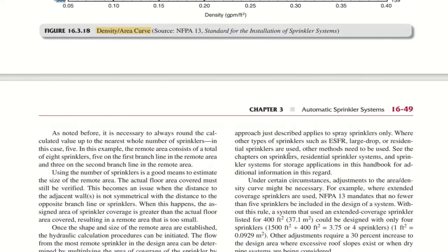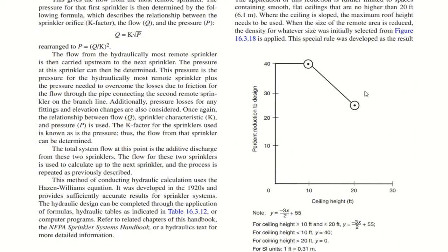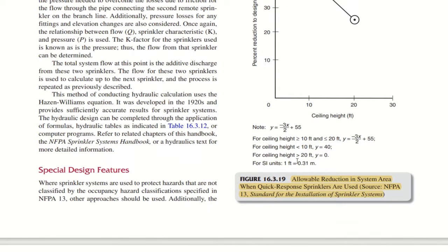If we consider quick response sprinklers in light hazard, then the density will be 0.1 gpm per square feet. However, the area of sprinkler operation can be reduced. So the hydraulically designed area can be reduced. That can be found from this graph. So this also I discussed in our NFPA 13 series. You can go through that.